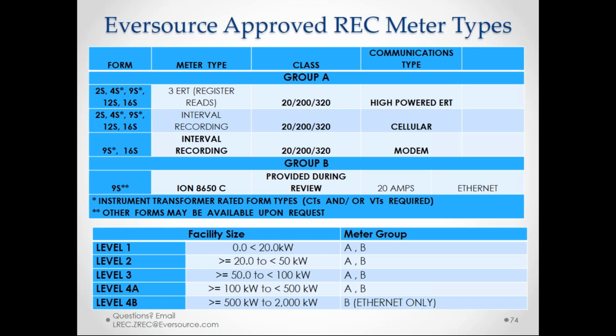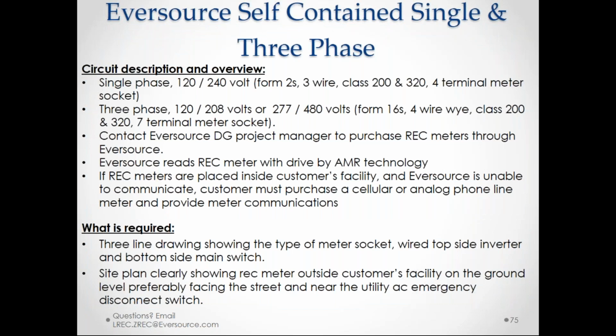So again, this just outlines some of the sizes that make things fall into certain categories. Our self-contained meters are rated up to 320 amps, so when you do your calculations on what your PV system is going to generate, generally if it's 320 amps or less, you're talking about a self-contained meter, whereas if you're talking over 320 amps, that's when you're going to need to go to a CT-based meter, where you're going to need to purchase and install CTs, possibly VTs as well.